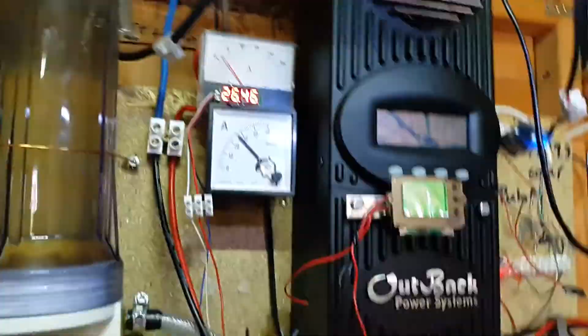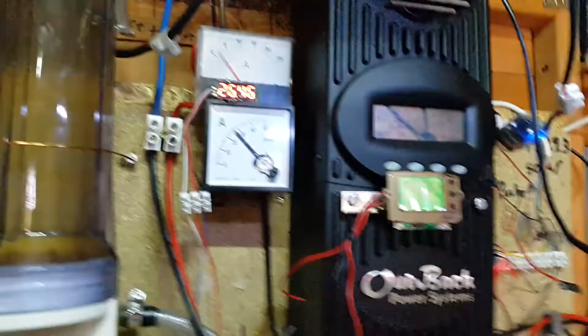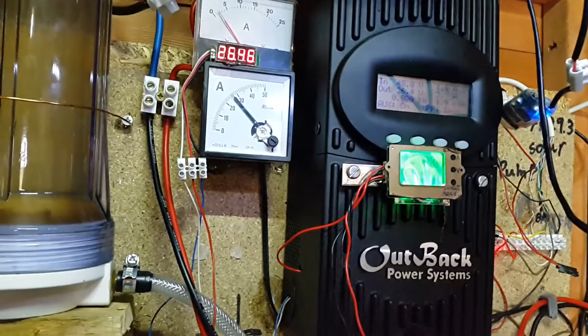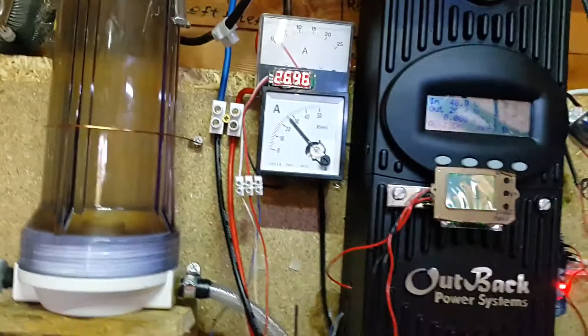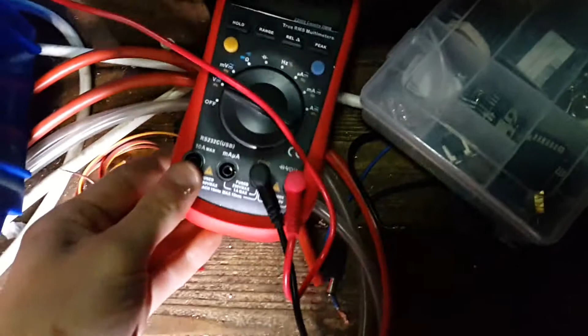I had my multimeter on the battery the other day, or it was today actually. When the grid tie inverter was pulling about 25 amps, the voltage on the battery was only dropping 0.06 volts, and that's just because the internal resistance is next to nothing. So I just want to do a voltage drop test. I'm measuring it direct at the battery terminals.